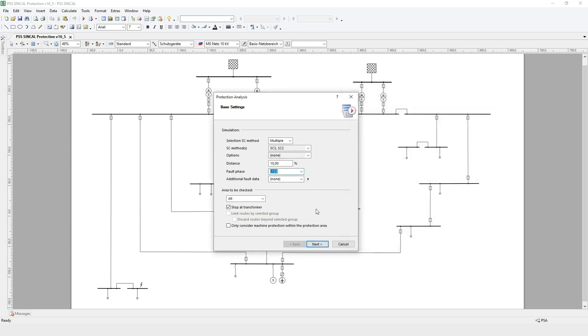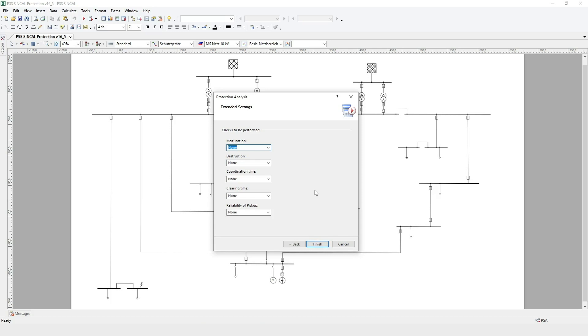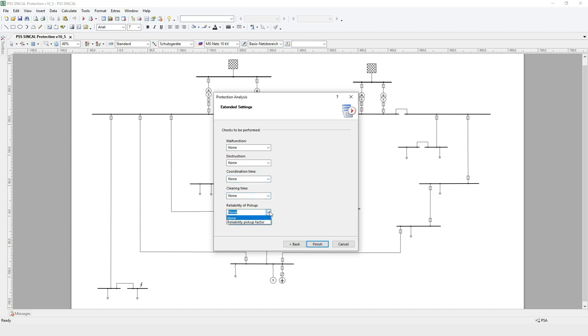In the area to be checked section, you can limit the protection analysis, which is useful in large networks. The second page of the dialog includes extended settings where you can activate and set the three most important checks in protection: selectivity, speed, and reliability. You can also decide if you want to perform the analysis for backup protection in case of a device or breaker malfunction.